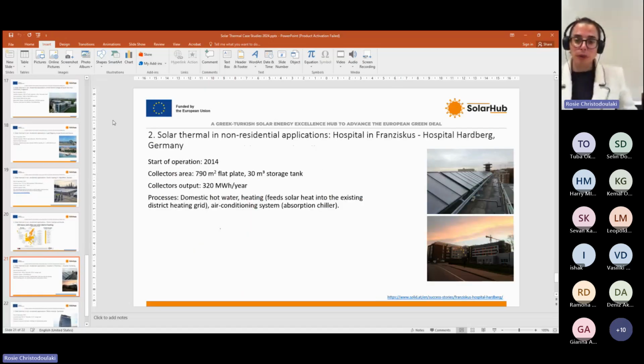Now let's continue to the non-residential applications, and more specifically a hospital application in Germany. As I said earlier, hospital applications are typical applications for solar thermal systems. This system started operation in 2014. It consists of approximately 800 square meters of flat plate collectors and has a storage tank capacity of 30 cubic meters of hot water.